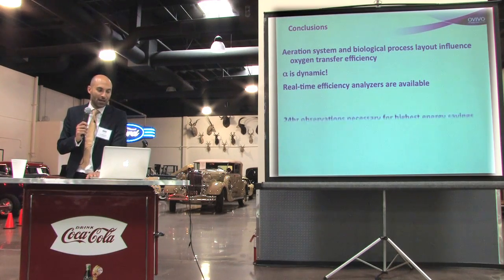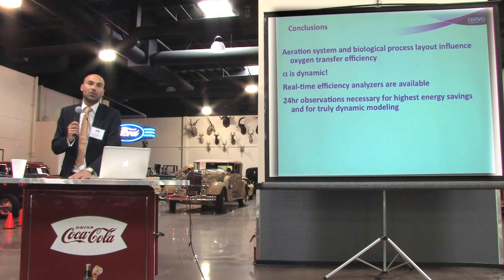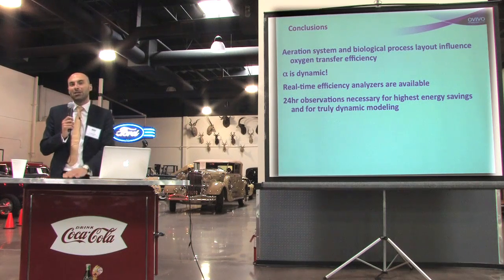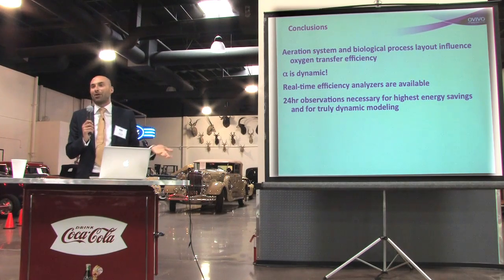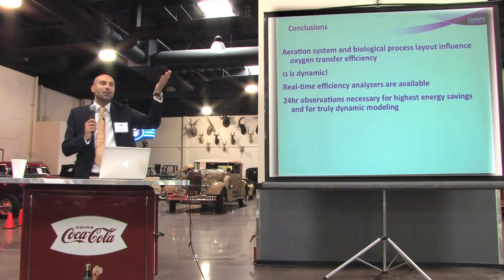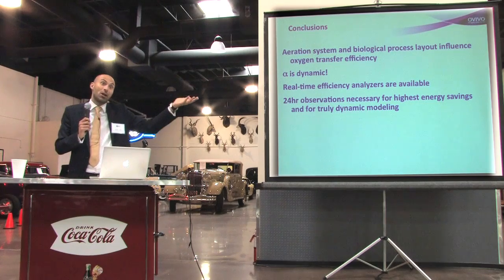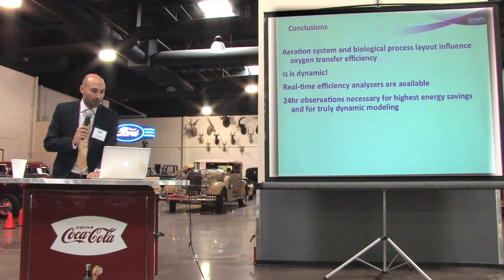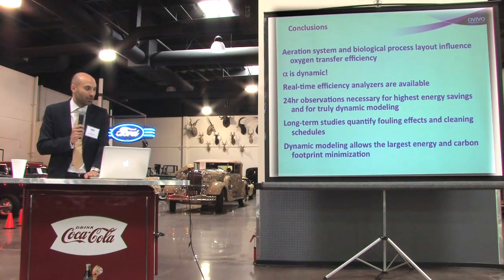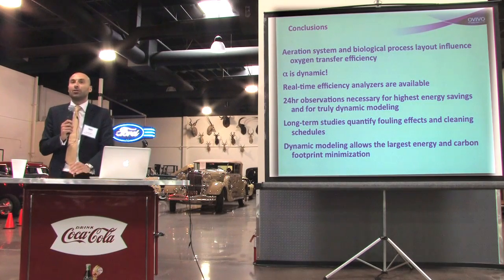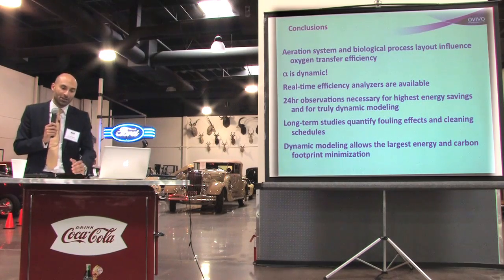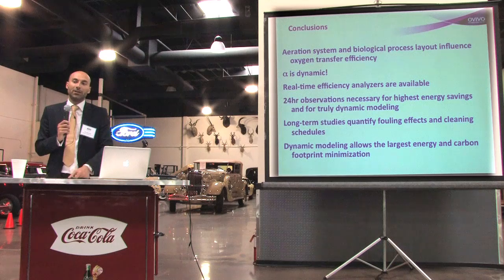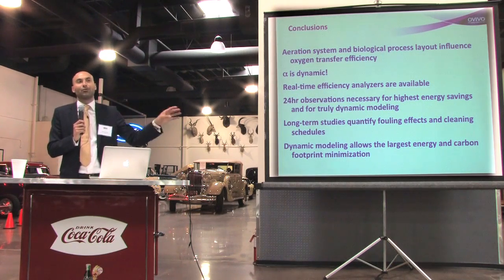To wrap up: process layout influences aeration efficiency — high SRT versus low SRT matters. Alpha is dynamic; you cannot give a meaningful alpha over the phone because it is site-specific and varies with the peak load, not just the average. The 24-hour observation is crucial for understanding what to design for. It's also important to maintain separation of roles — as an operator or design engineer, don't take on the liability of interpreting manufacturer data without independent help. Send me an email and I'll share relevant papers.